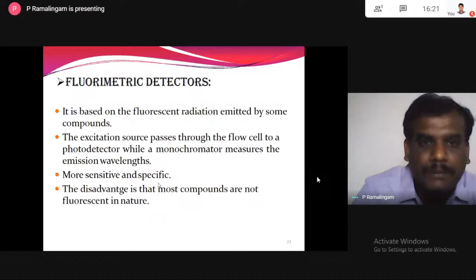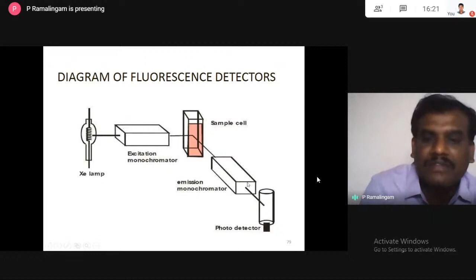It has an excitation monochromator, and the light goes to the sample. Here the fluorescence is measured at a 90 degree angle. The fluorescent intensity will be very high at 90 degrees to the incident beam. Then there is the emission monochromator, and after that we have the photo detector.